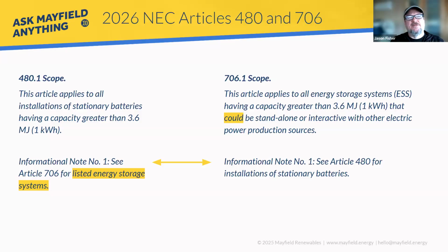I think it's finally resolved, but even last cycle there were attempts at trying to make this a little clearer about when you'd use one article over another. Ironically, the way the code making panel resolved this was just to say, well, it's not up to the National Electrical Code to say when you install a battery system or when you install an energy storage system. The point of the NEC, because it's an installation code and a safety code, is: if you are installing one of these, here is how you do it safely.